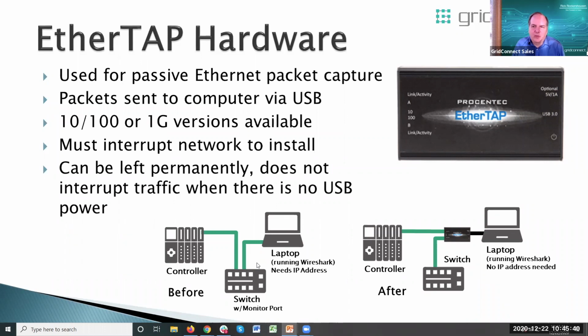But nonetheless, if you want to run Wireshark, this is how you had to do it. This new product called the Ether Tap—it's not so new, it's been around a while—basically goes between the switch and the controller. You come into the Ether Tap and out, and there's a USB link over to your laptop, so you don't have to go through the hassle of setting up an IP address or finding which one to use. Of course, installing this Ether Tap would require unplugging the cable from the controller to the switch, so there's an interruption the first time you install it. But if you leave it installed, you do that once during downtime, and then you're ready to go whenever you want to do analysis.